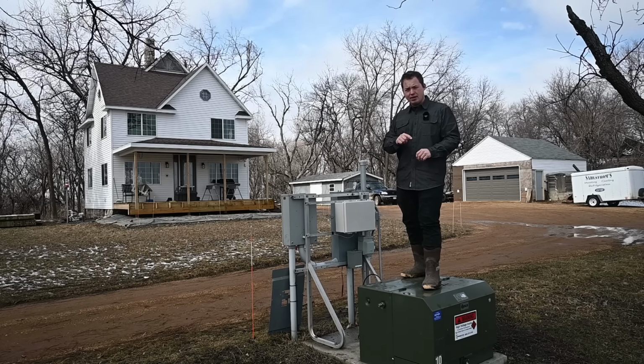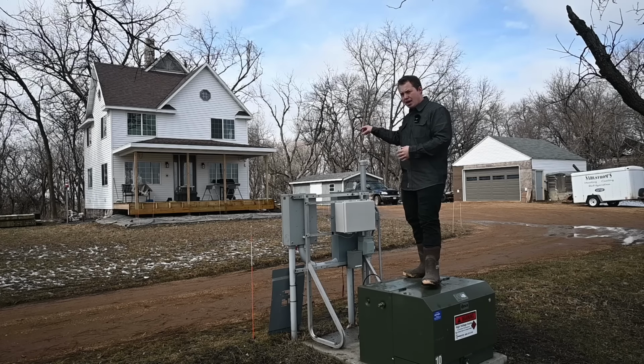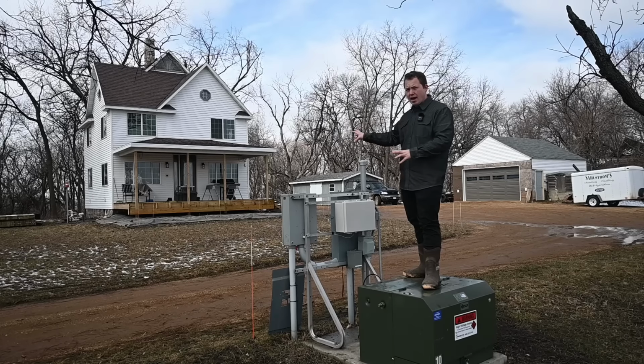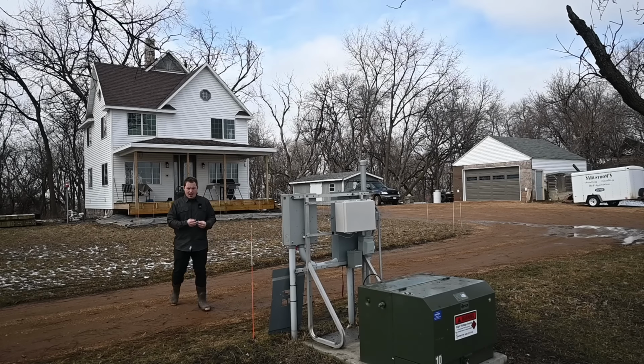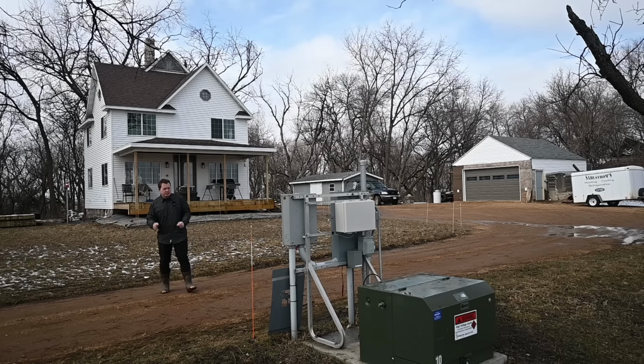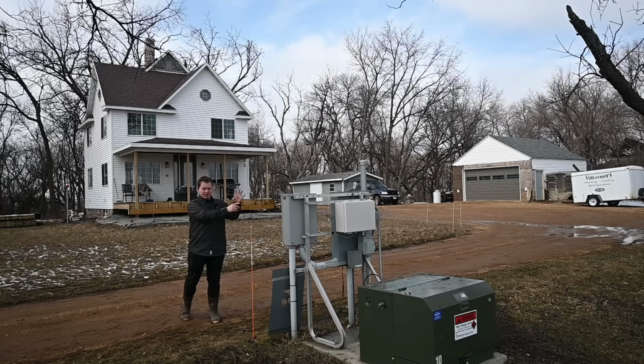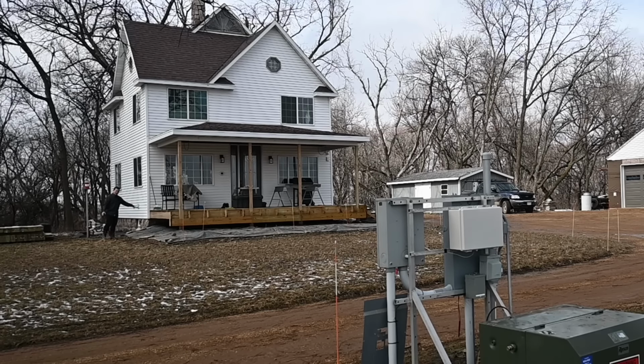The center tap of the transformer, which is the neutral, then goes into that panel and is tied onto the grounding system. So at that point is where that current gets dissipated through my grounding system. And at any point where there is a decent grounding electrode, some of that current is being distributed through that electrode. So we have electrodes here in the ground that are connected to this panel. And then we have grounding electrodes over here by the house that are connected to the panel inside there that we've been looking in. There's a ground rod right about here and a ground rod over here. So a percentage of the current is leaking through the grounding electrodes right there.